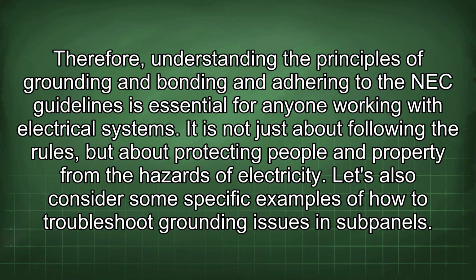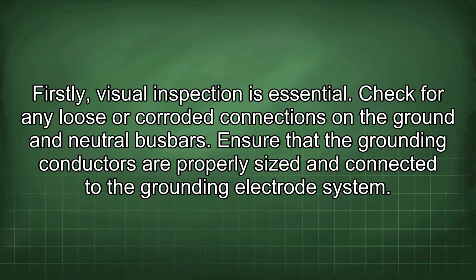Therefore, understanding the principles of grounding and bonding and adhering to the NEC guidelines is essential for anyone working with electrical systems. It is not just about following the rules, but about protecting people and property from the hazards of electricity. Let's also consider some specific examples of how to troubleshoot grounding issues in subpanels. Firstly, visual inspection is essential. Check for any loose or corroded connections in the ground and neutral bus bars. Ensure that the grounding conductors are properly sized and connected to the grounding electrode system.